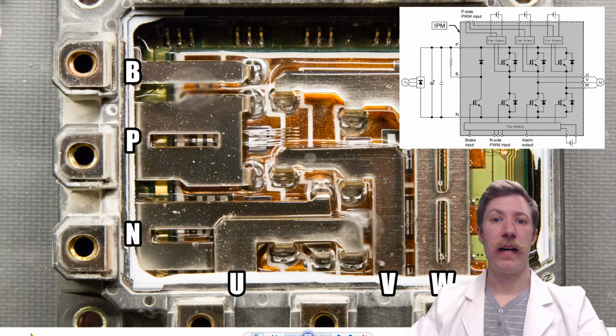Let us start out by getting an overview of the IGBT brick internals. Now here I have marked up the 6 power terminals of the IGBT brick. We have the B for brake, P for positive, and N for negative. Then we have U, V, and W, the 3 motor outputs.